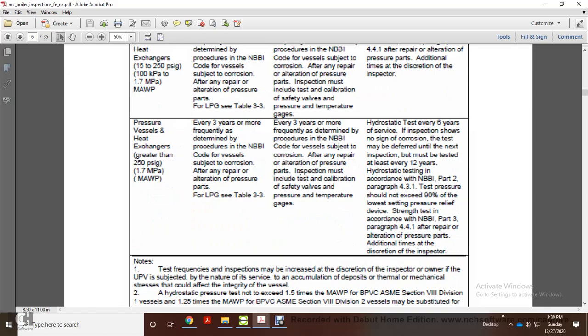Pressure vessels and heat exchangers greater than 250 psi gauge: every 3 years, or more frequently as determined by procedure in the NBBI code for vessels subject to corrosion, and after any repair or alteration of pressure parts. Inspection includes testing and calibration of safety valves, pressure gauges, and temperature gauges. Hydrostatic test every 6 years. If inspection shows no signs of deterioration, the test may be deferred until the next inspection, but must be tested at least every 12 years.